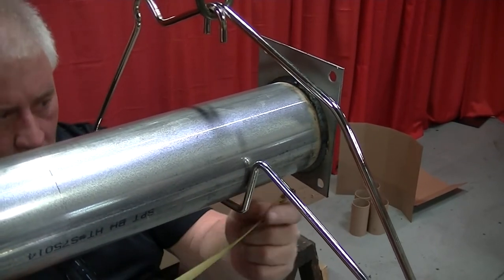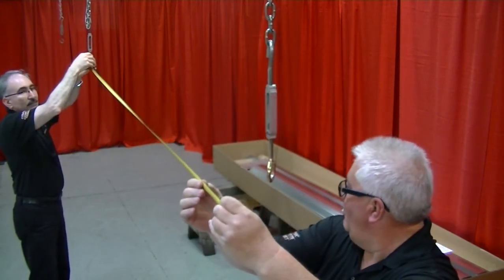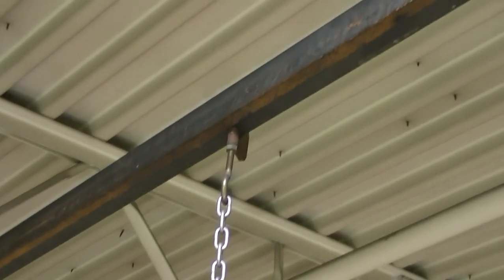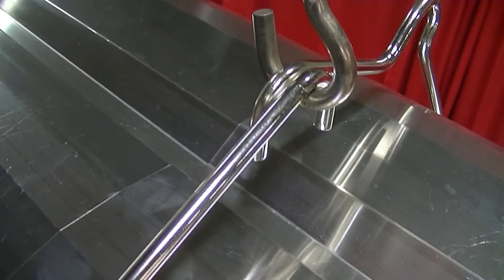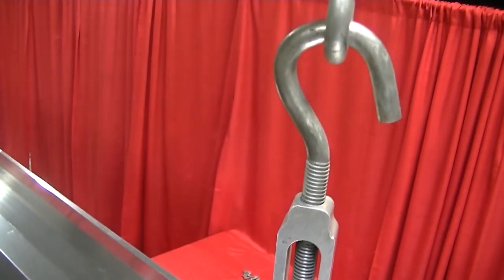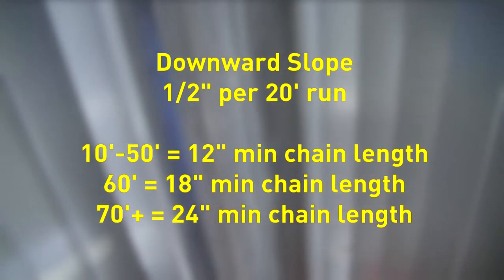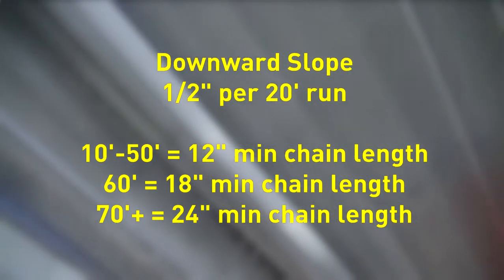The first hanger must be positioned within 4 inches of the burner. The second hanger should be located 7 feet 6 inches from the first hanger. All other hangers thereafter are spaced 10 feet apart. Properly securing unistrut or equivalent from the hanging points may be required to ensure proper spacing. When hanging chain, it is recommended to use turnbuckles with S-hooks to maintain the minimum chain length and appropriate slope away from the burner. Tubing requires a downward slope of 1/2 inch per 20-foot run. For heater lengths between 10 and 50 feet, the minimum chain length is 12 inches; 60-foot heaters require 18 inches; heaters 70 feet or above require 24 inches.